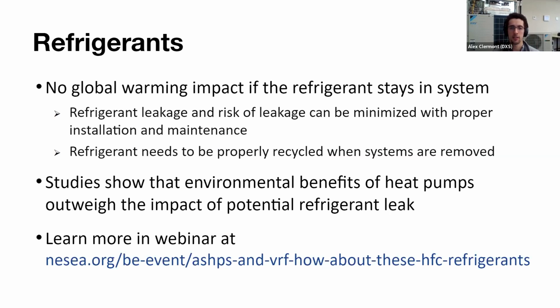Again, the environmental benefits of using heat pump technologies outweigh the impact and potential chance for a leak. Fear not, R410A is not going away soon. All these systems for the foreseeable future will be in R410A. It will continue to be available for the next few decades, just like R22 was available for a few decades for service of existing equipment. We're excited about the arrival of R32 as a next generation refrigerant, as it can have higher efficiencies, lower GWP, and just overall less of it. But in the meanwhile, R410A systems are safe to install and go through their life with no problem. We just have to focus on quality install and keeping the refrigerant inside of them. Next, I'll pass it over to Mike to talk to us about efficiencies.